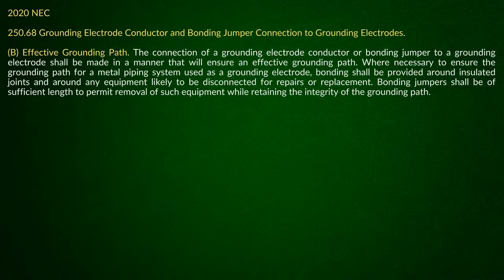This is the installation, but you're going to be looking at B, making sure you're providing that effective grounding path. Matter of fact, we even show one if I went outside and I was tying into another electrode and somebody came out and it was in conduit, you would have to bond that conduit with that grounding electrode conductor. Okay, sure. We show that in another illustration.